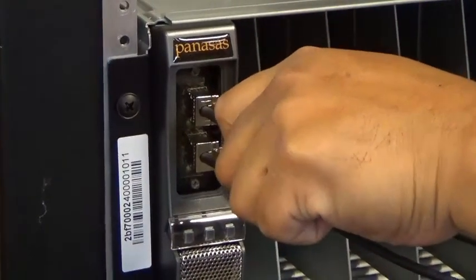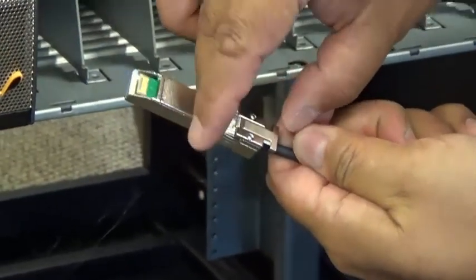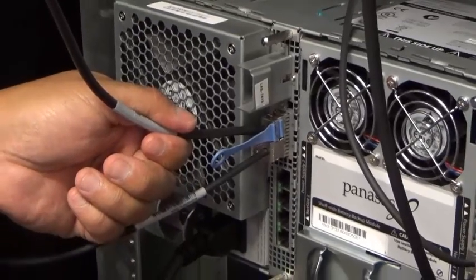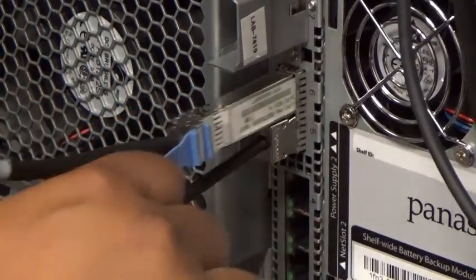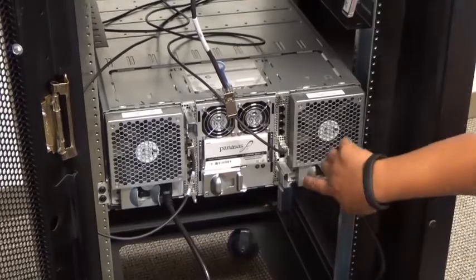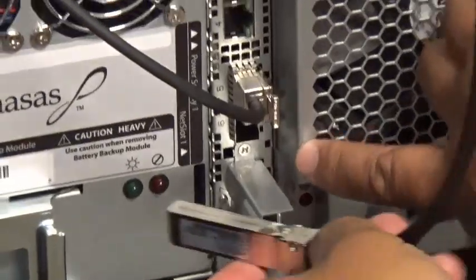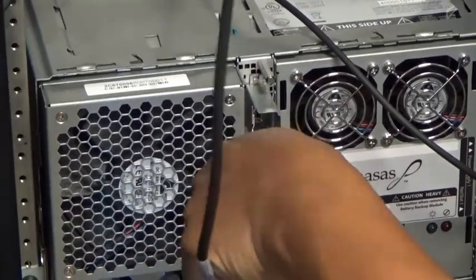To insert twin X cables, you push until you hear an audible click. To release them depends on the variety of Twinax cable. In this case, you push the lever in, which then releases the Twinax cable. Where there is a pull tab, you will have to pull the tab to release the Twinax cable and then it will come out easily. Now that we have the switches installed and the cables from front to back installed, we'll connect the cables from the customer's network into the port six sockets on each of the net one and net two switches.